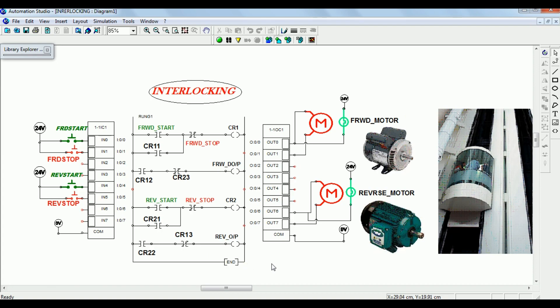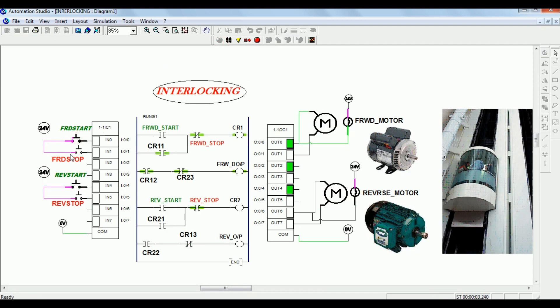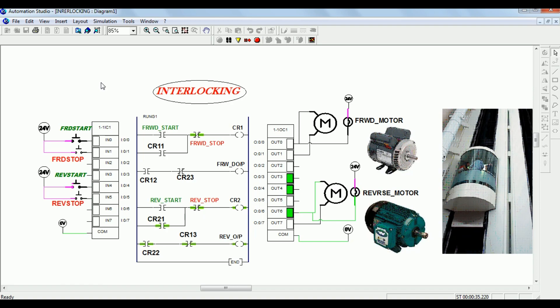Carefully see the ladder diagram for interlocking — how the switches are used and how they are interlinked. In the simulation, when the forward motor gets ON and you try to start the reverse motor by pressing the switch, you don't get any output for the reverse motor. To get the output for the reverse motor, you have to first stop the forward motor. Similarly, to get output in the forward motor, you have to first stop the reverse motor.